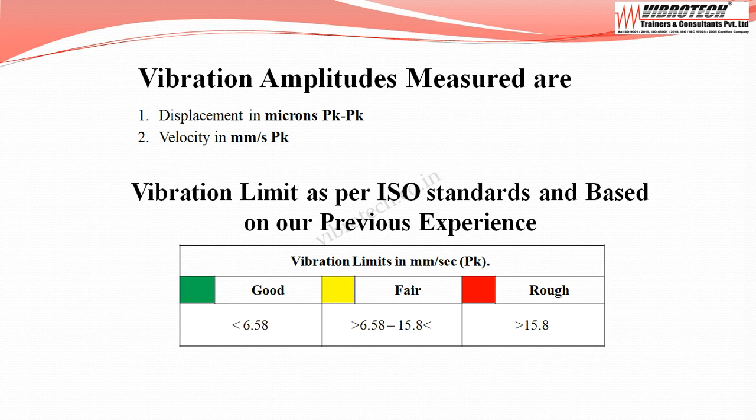As per ISO standard and our previous experience, the vibration limits are as follows: when the velocity falls below 6.58 mm per second peak it is considered good; between 6.58 to 15.8 mm per second peak it is considered fair; and above 15.8 mm per second peak it is considered rough.